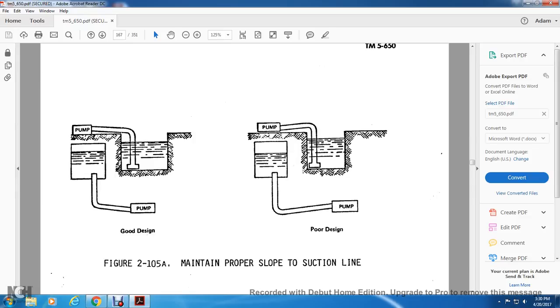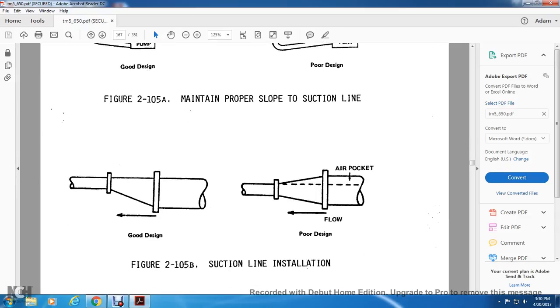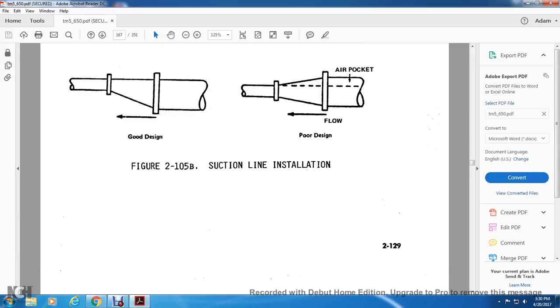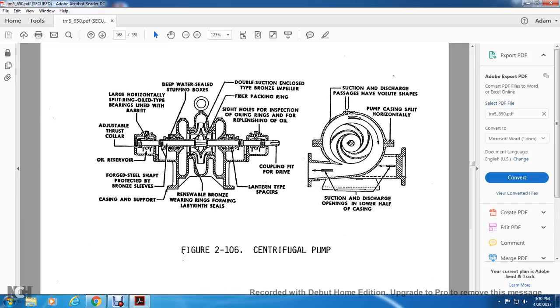Pump, good design. Pump, poor design. Suction line installation, good design. Poor design: air pocket in the flow. Centrifugal pump, starting on the right: suction and discharge passages have volute shape. Pump casing split horizontally, with suction and discharge openings in the lower half of the casing. Starting at the double suction closed type bronze impeller, moving clockwise: fiber packing ring, with sight holes for inspection, oil rings, and oil replenishing, coupling for the drive, lantern spacers, renewable bronze wearing rings forming labyrinth seals, casing support, forged steel shaft protected by bronze sleeves, oil reservoir, adjustable thrust collar, large horizontal split ring oil type bearings lined with Babbitt, and deep water seal stuffing boxes.